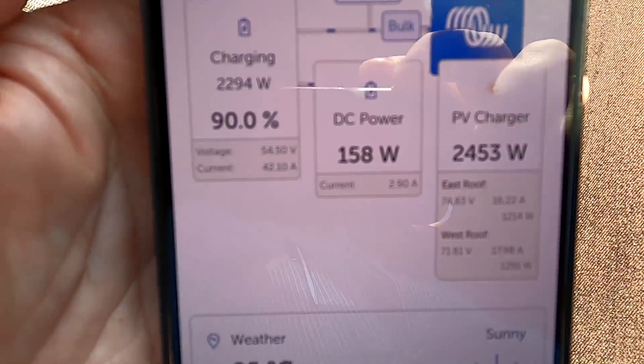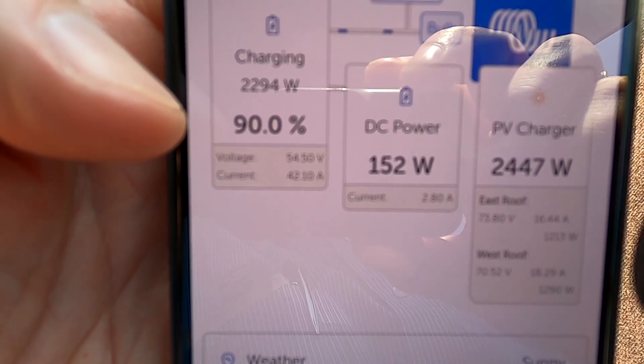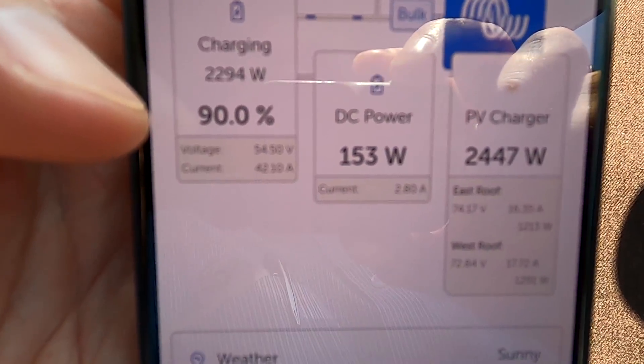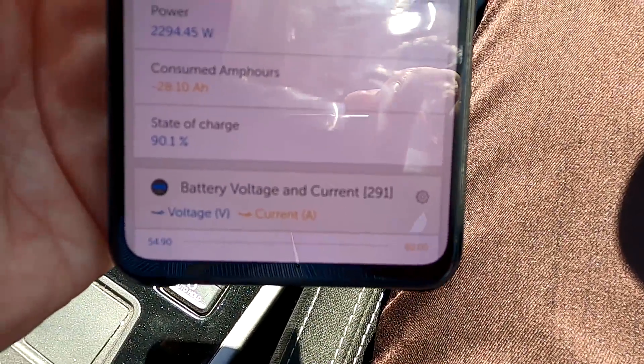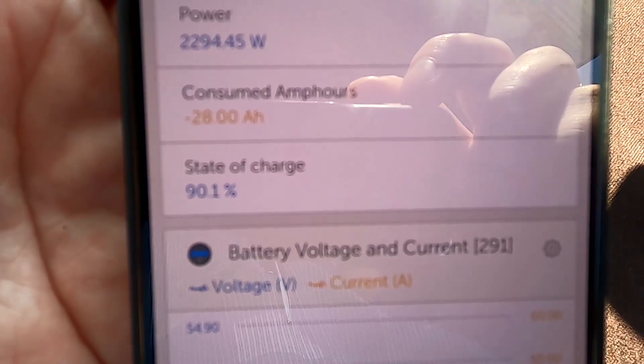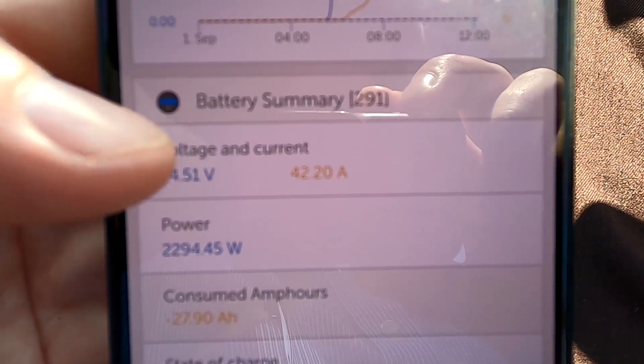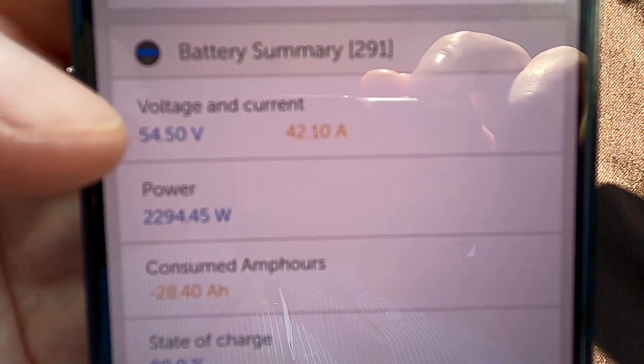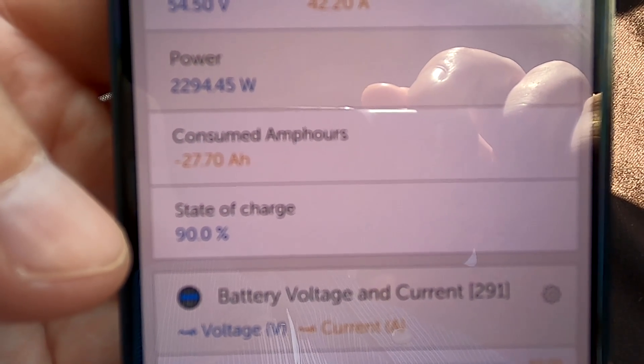It is now the next day and we have just hit the 90% mark state of charge. We know after yesterday's calibration that 100% is 100%, so if you want to charge to 90% we should stop right now. Let's wait until we hit 55.2 volts and then have another look at how many ampere hours we have left until zero — this gives us the percentage we are charging to.